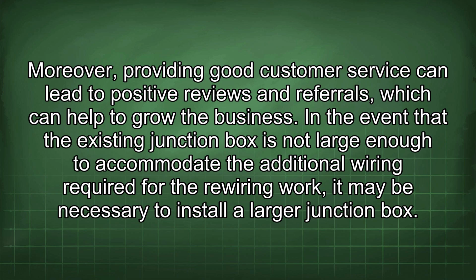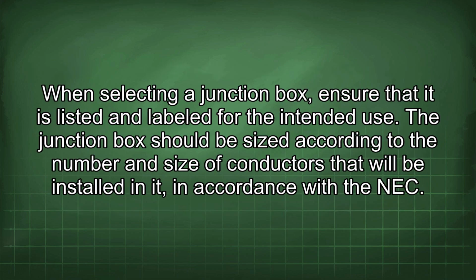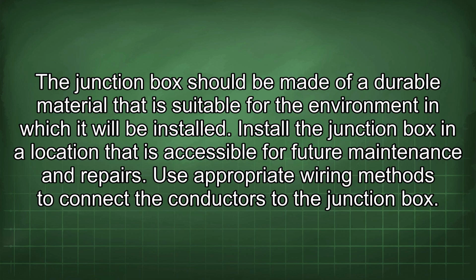In the event that the existing junction box is not large enough to accommodate the additional wiring required for the rewiring work, it may be necessary to install a larger junction box. When selecting a junction box, ensure that it is listed and labeled for the intended use. The junction box should be sized according to the number and size of conductors that will be installed in it, in accordance with the NEC. The junction box should be made of a durable material that is suitable for the environment in which it will be installed. Install the junction box in a location that is accessible for future maintenance and repairs.